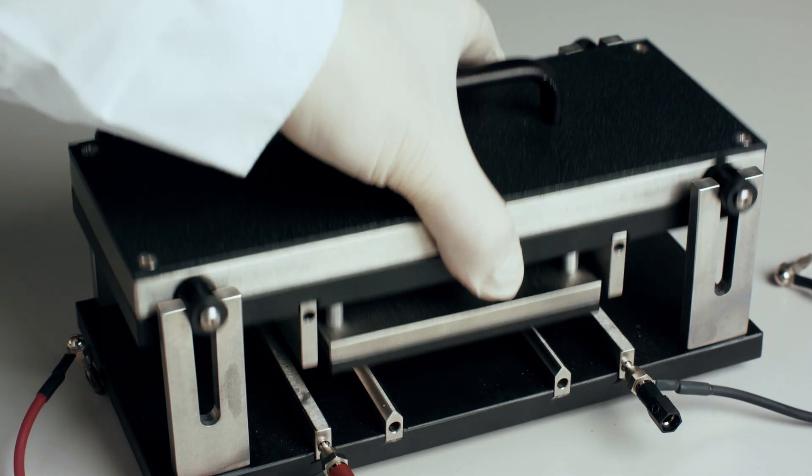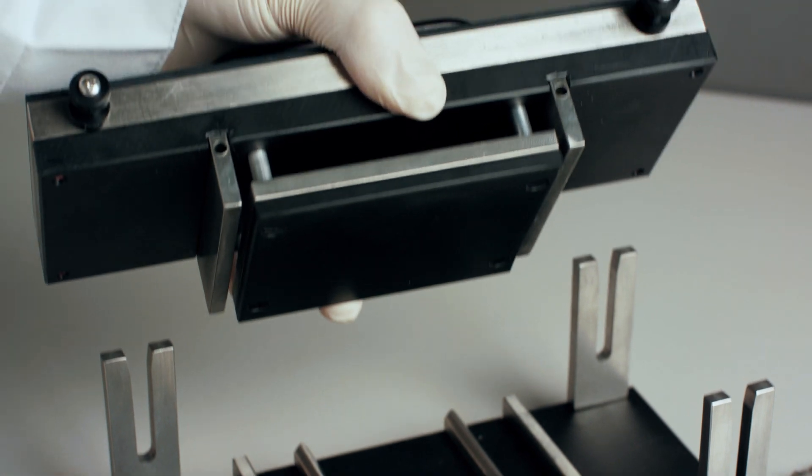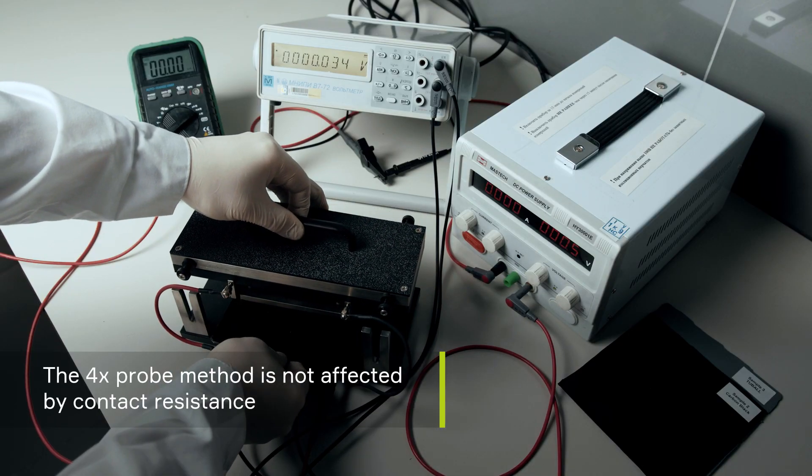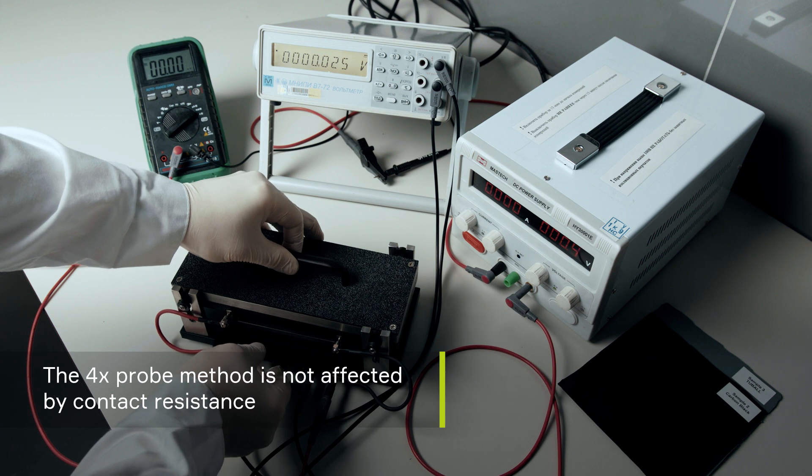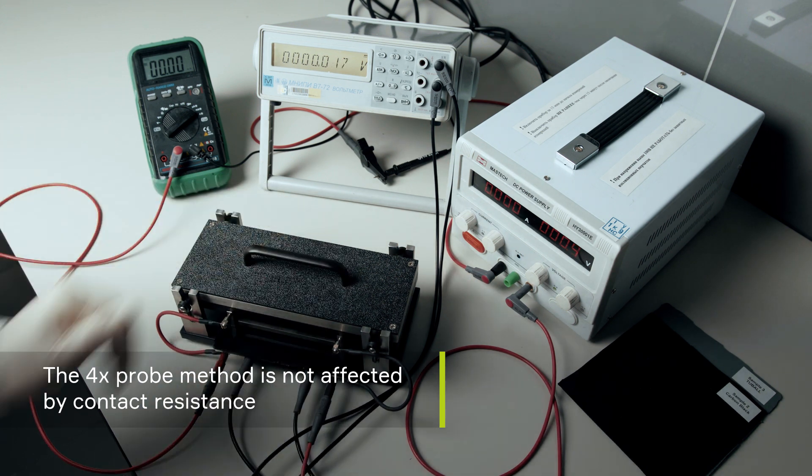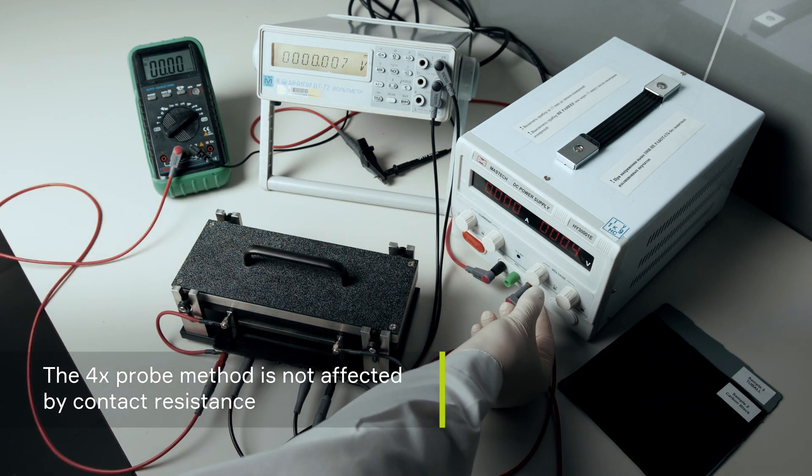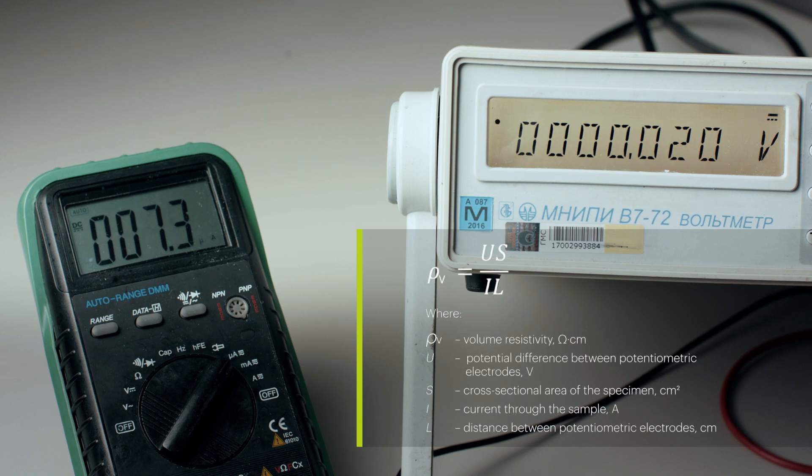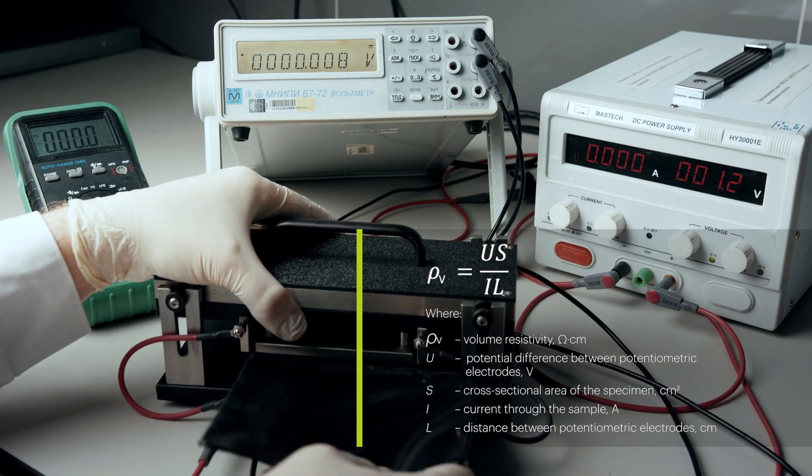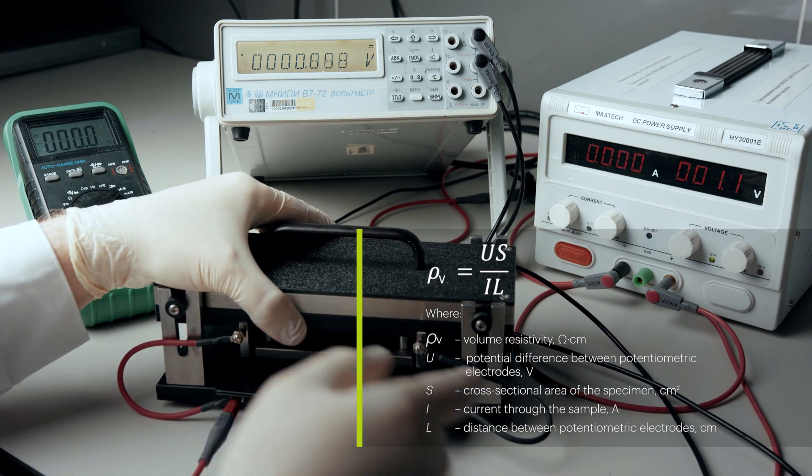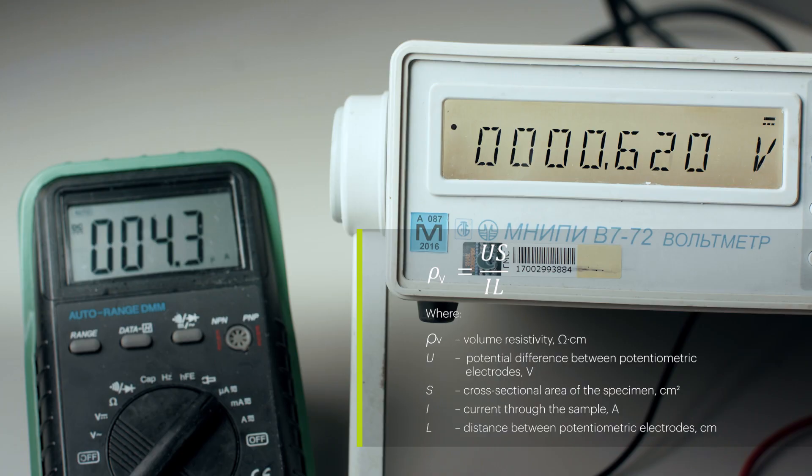The measurement takes into account the distance between the electrodes and the dimensions of the sample. It is not affected by the contact resistance that occurs between the attached electrodes and the sample. The 4 probe method allows us to determine the actual resistance of the material, which can then be converted into the volume or surface resistivity using the formula.